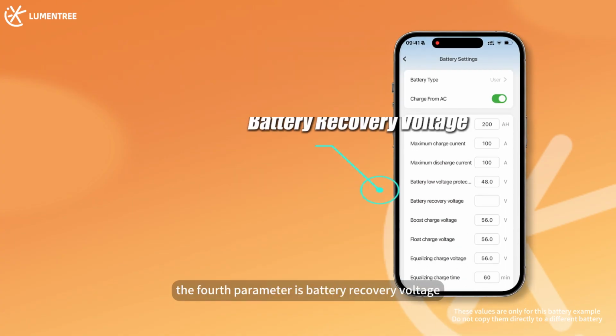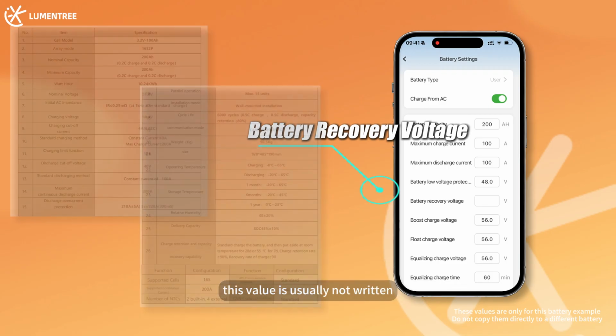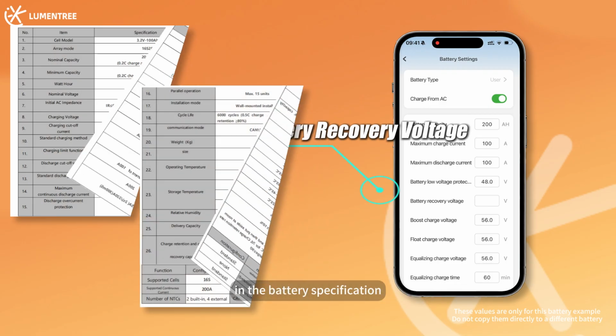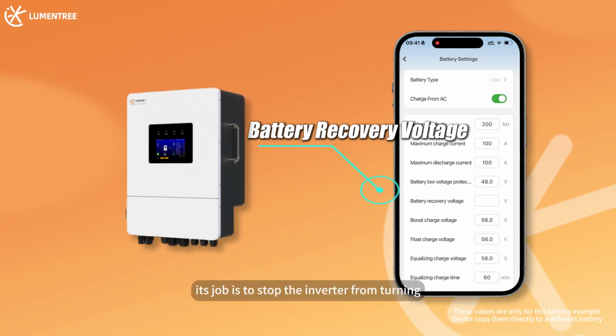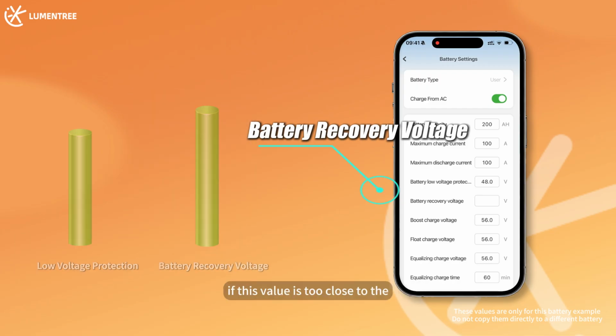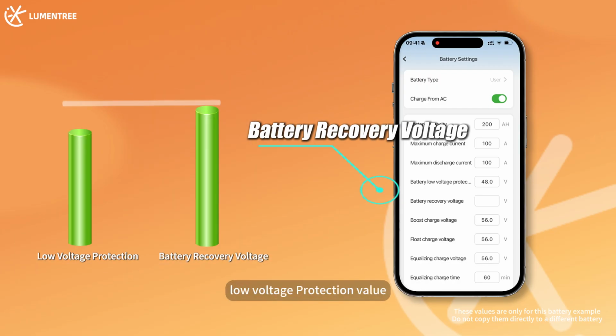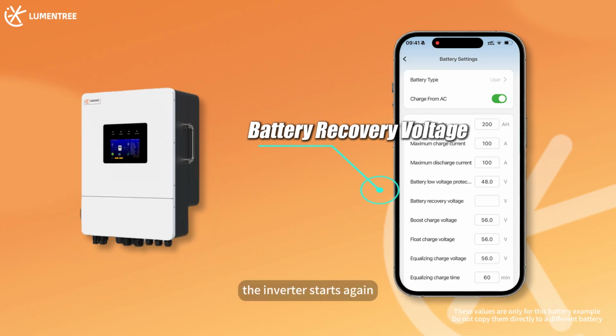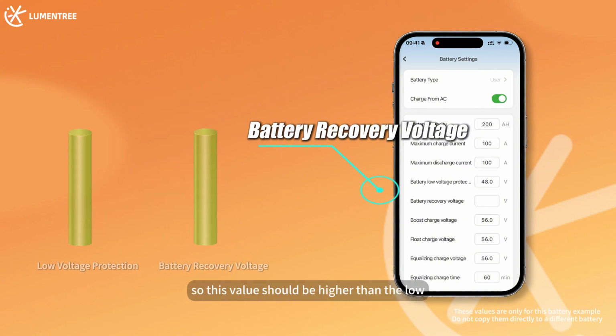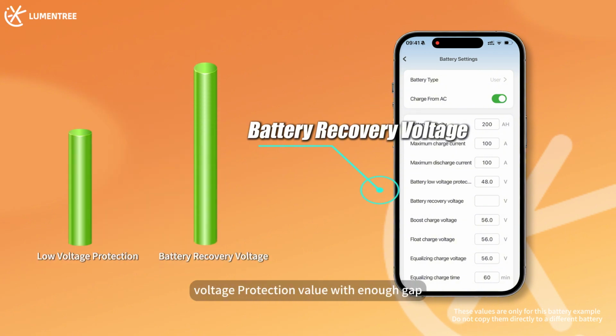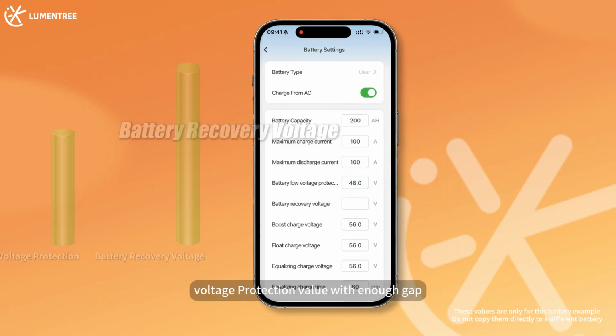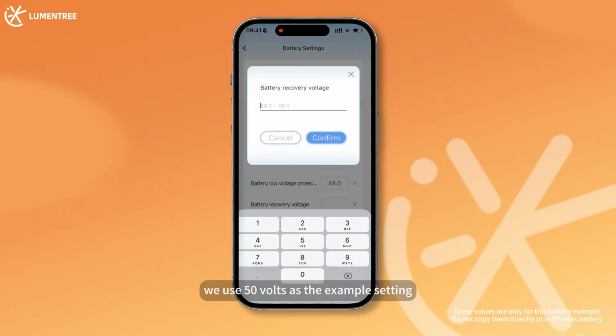The fourth parameter is battery recovery voltage. This value is usually not written in the battery specification. Its job is to stop the inverter from turning on and off again and again at low voltage. If this value is too close to the low voltage protection value, the battery voltage may rise a little. The inverter starts again and then shuts down again when the voltage drops under load. So this value should be higher than the low voltage protection value, with enough gap. For this battery, we use 50 volts as the example setting.